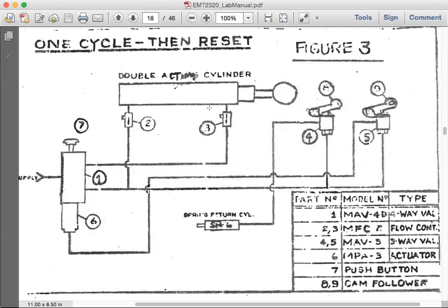So all the pressure from the right chamber and from this hose is right now venting, and the pressure from the supply is redirected through the bottom port and comes right here, provides the pressure to the left chamber of the double acting cylinder, and continues and splits 2 more ways to go to the bottom of number 4 and number 5.